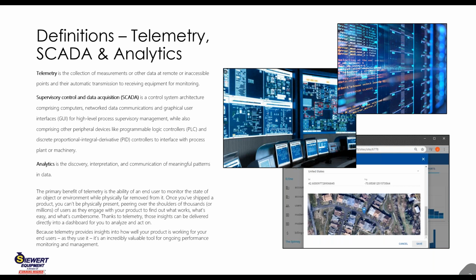It's a control system architecture comprising of computers, network data communications, and the powerful part, the graphical user interface. You can see the screenshots I've got up there. The top left or middle left is something very common that I've seen in larger municipalities, larger wastewater and water plants across the United States. They do everything from tracking trucks, their service vehicles, the position of panel doors, what valves are open and shut, what booster pumps they have running, feed pumps they have running. In truth, most with a system this advanced, short of the boots on the ground in the field, can run the vast majority of their plant from inside a nice air-conditioned office.